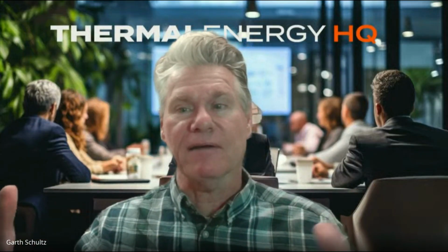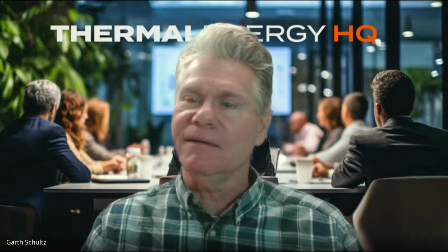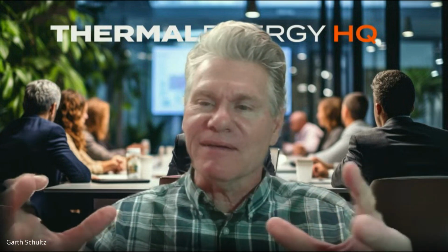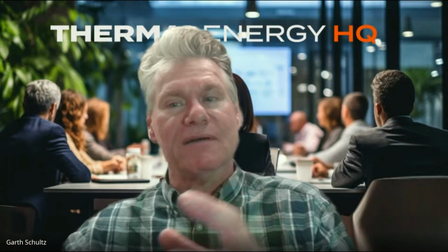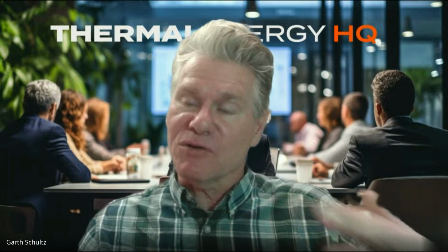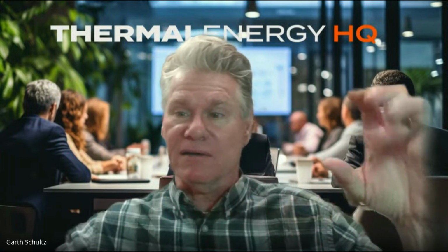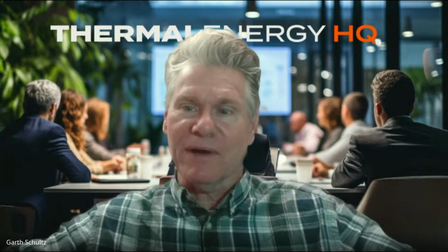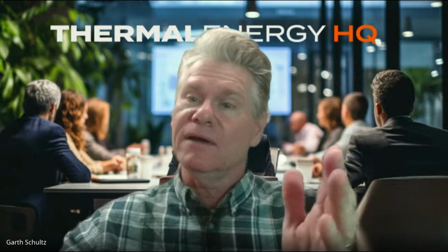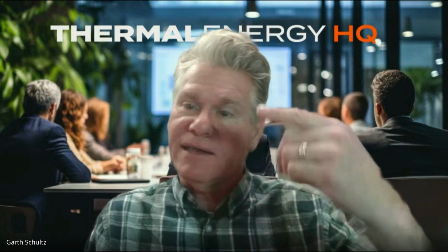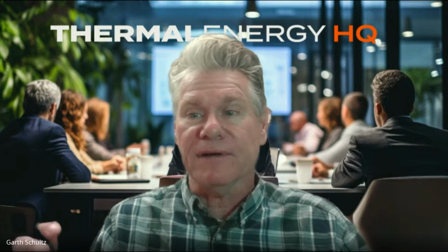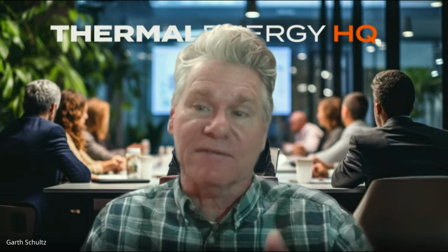We're thermal. So if you're going to bank it, let's say you had that PV system running a device to cool a house or heat water, that's where the storage potential would lie. Is it a week? Depends - we're mainly on the diurnal, or daily, storage relevancy, but it allows you to most efficiently operate your PV system. Because if you've got no loads and the sun's out, and your battery banks are full, what are you going to do with that incoming energy? You can store it for use wherever the solar system is, next to the building, house, school, or hospital, and utilize that thermal energy there. It gives you the capability of enabling your solar system to run most effectively for you and your client.